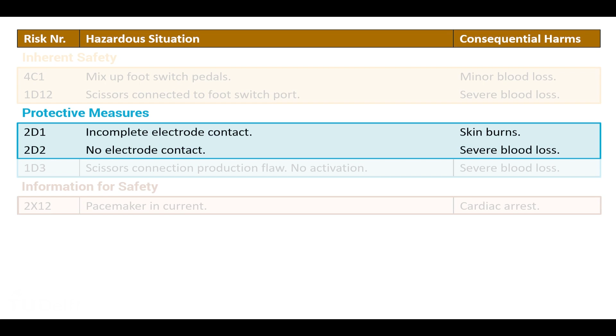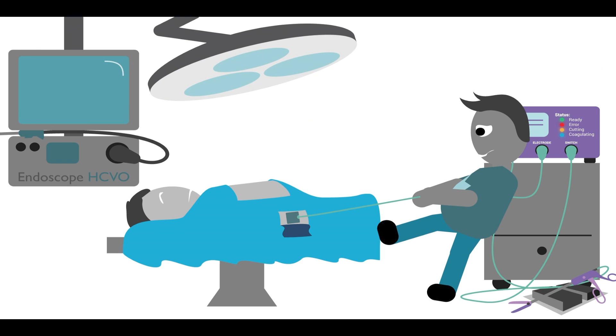Now, the issues with improper adhesion of the return electrode could maybe be improved a bit by using better sticking and conducting glue, but that will make removal of the patch bad for the skin. If the adhesive layer would be made to conduct extremely well, the patch will also work with a small contact area. But then the current density will become too high and cause skin burns.